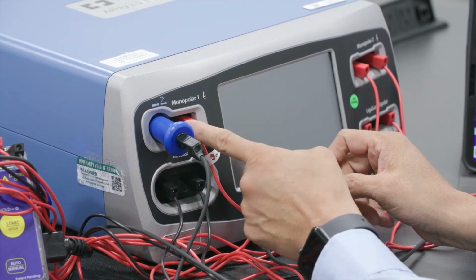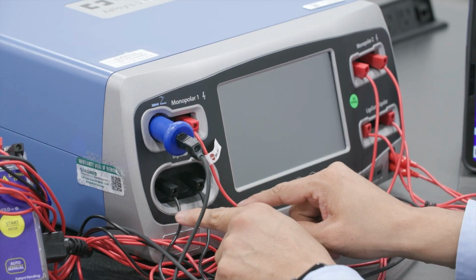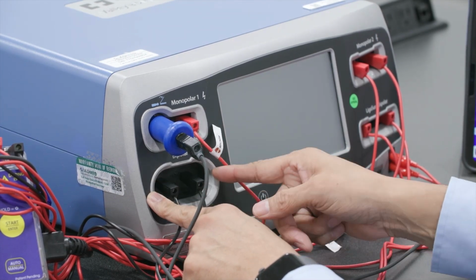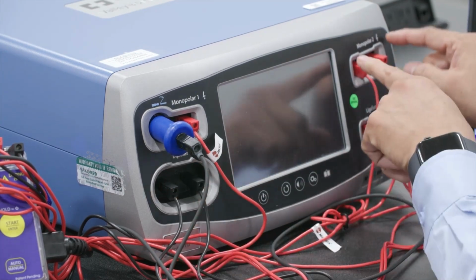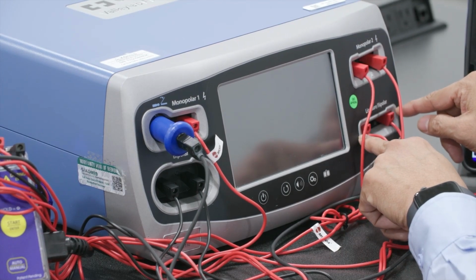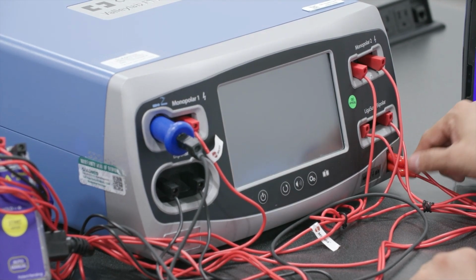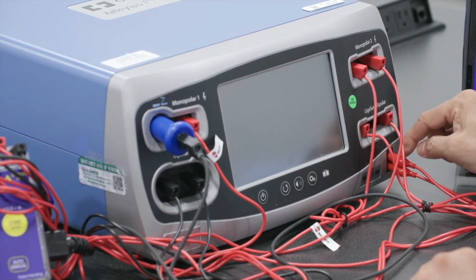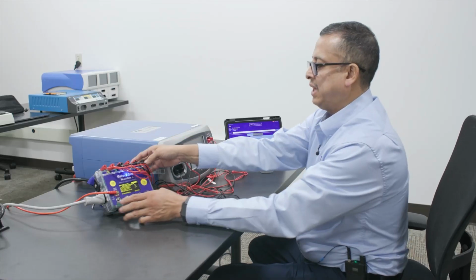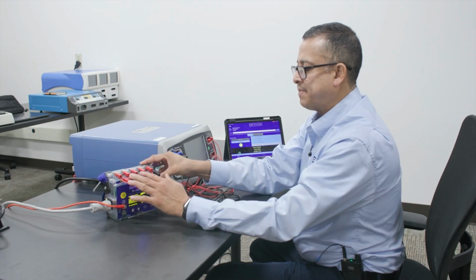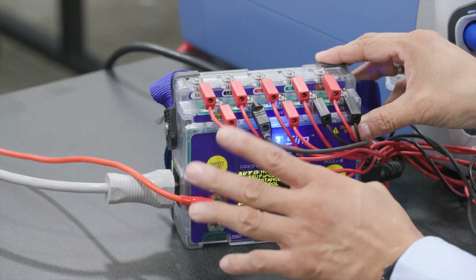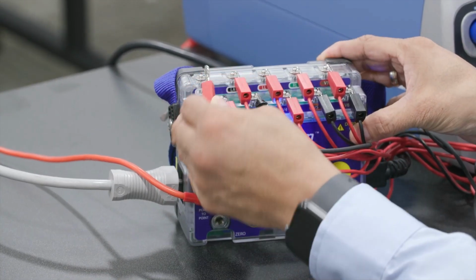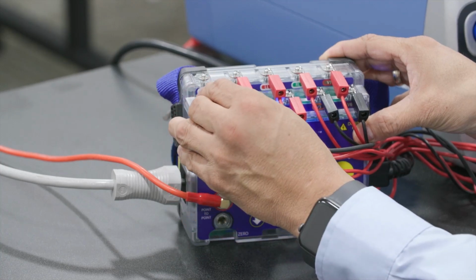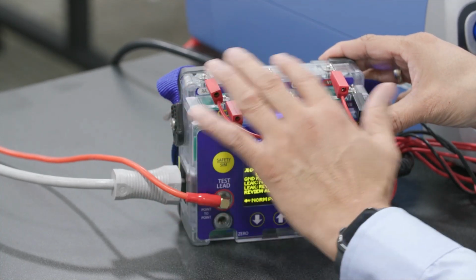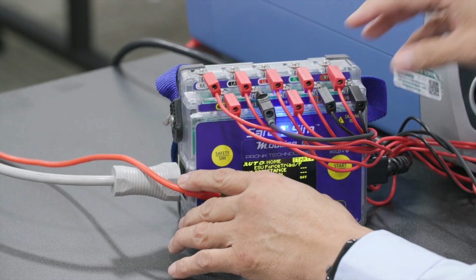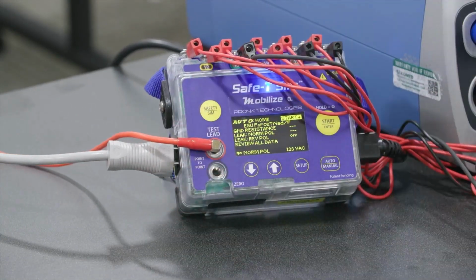And then the right side goes into the far right port, and the same thing is true for the other ports. You put a lead wire in the far left, and then in the far right for bipolar, same with monopolar 2, and same with the lower right hand port. And of course our REM line, you want to connect two test leads to that as well, all connected to our electrical safety analyzer here on the left. So you connect it to the snaps. It doesn't matter which snap you connect the wires to, they can connect in any order you want, by simply taking a banana plug and sliding it in underneath the snap. So there's enough room to connect all of the leads to the electrical safety analyzer to do our testing.